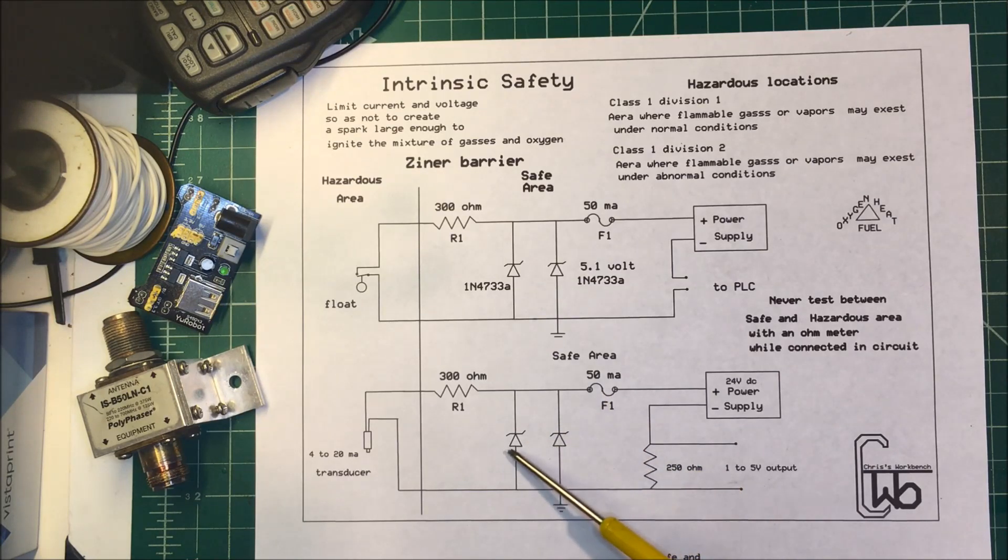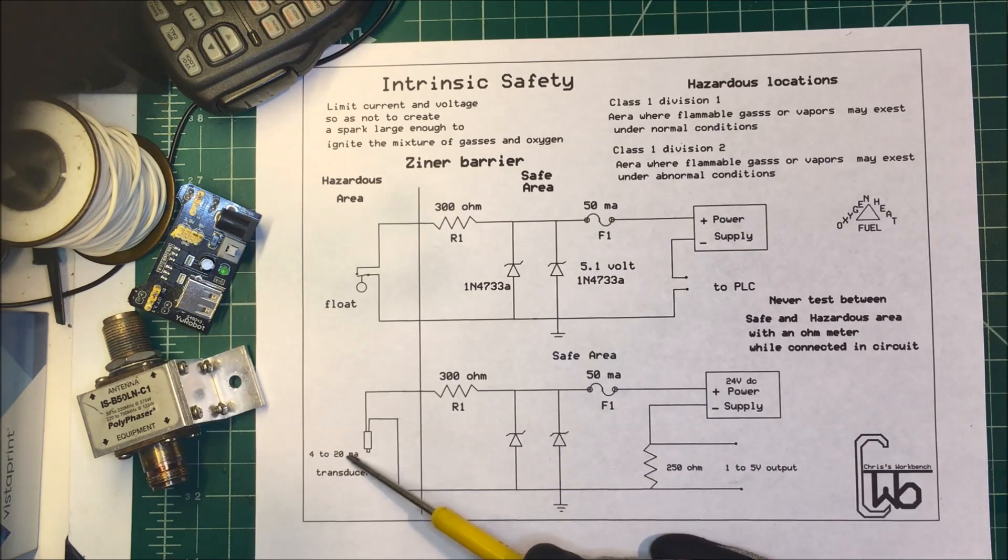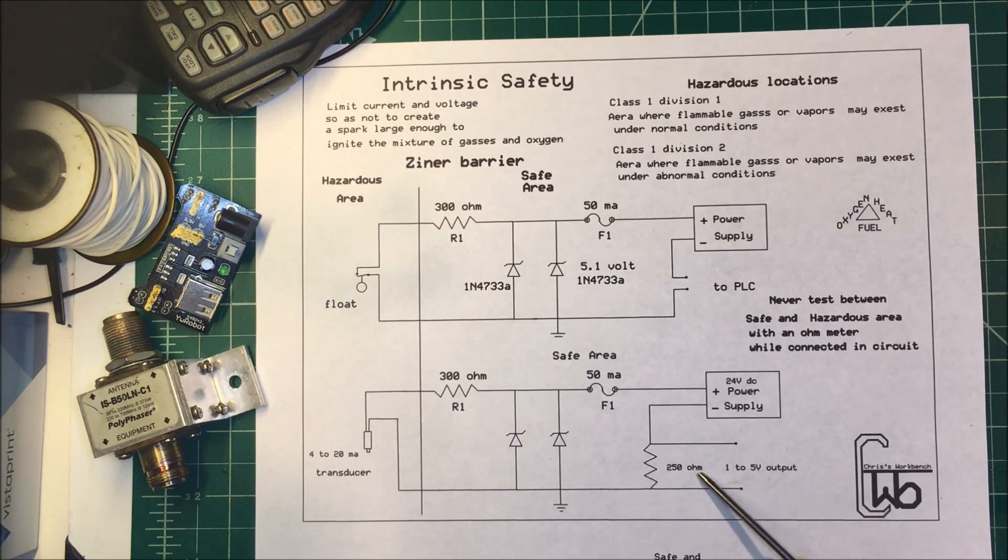And then a resistor to limit the current. In this case, we're running power through here. This puts out 4 to 20 milliamps and we come back to a 250 ohm resistor.